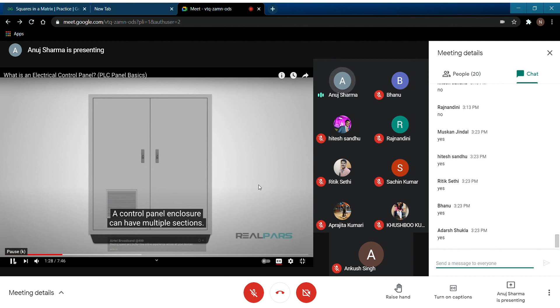Let's get started. First, let's talk about the enclosure, the metal box that contains all of the electrical devices of the control panel. Enclosures are often aluminum or stainless steel, and the size will vary based on the size of the process. A control panel enclosure can have multiple sections. Each section will have an access door. The size of the enclosure is commonly referred to by the number of doors the enclosure has. Each enclosure will have an electrical safety rating designated by UL, the Underwriters Laboratories, who governs electrical safety. They will also have an IP rating, or NEMA classification, which designates the enclosure to be indoor or outdoor, waterproof or water-resistant, suitable for hazardous conditions, dustproof, or explosion-proof.